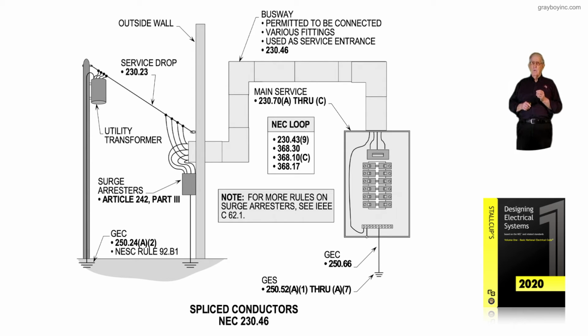230.46. However, we still recommend you review 230.43, item 9, 368.30, and 368.10(C), as well as 368.17 that deals with busways. Reviewing those sections will give you a better understanding of installing a busway and splicing it as permitted, and I'm talking about the buses, the busway, in accordance with 230.46. In this illustration, 6-25 illustrates such an installation.